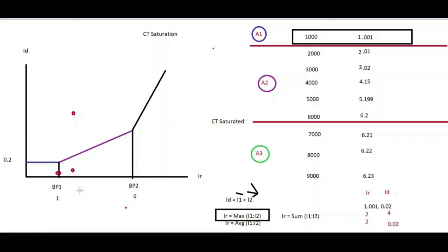Now what happens when the CT saturates? So far we were talking about 2000 amps. Now if you assume the fault current to be 8000 amps, the same thing holds good. So let's say the CT saturated, one side CT only will get saturated. Both the CTs will not get saturated. If both the CTs get saturated, there is no problem. Your system will work perfectly. Because 6.22 minus 6.22, it will again be 0. External fault CT saturation, relay will not trip. 6.22 plus 6.22, relay will trip. Internal fault CT saturation. So there is no problem. But the problem occurs when only one CT saturates. That is the worst case scenario.